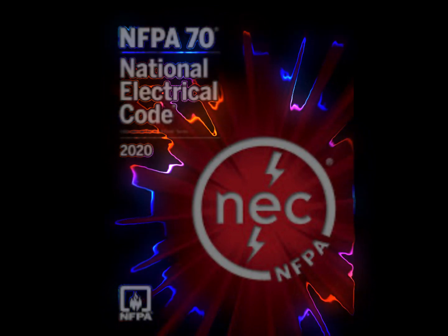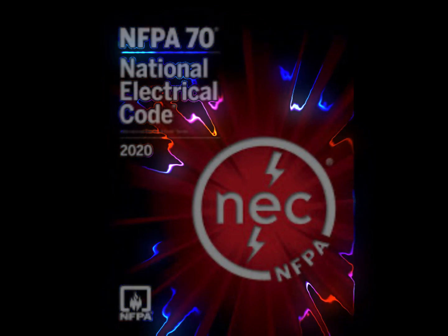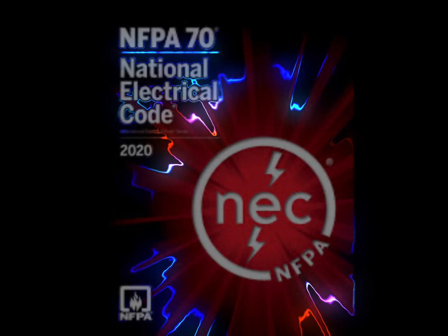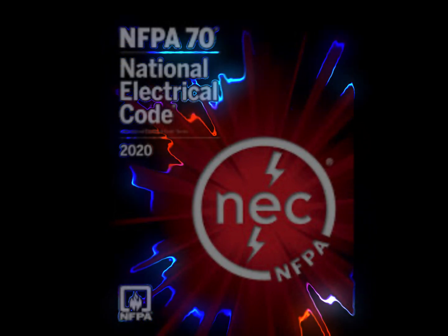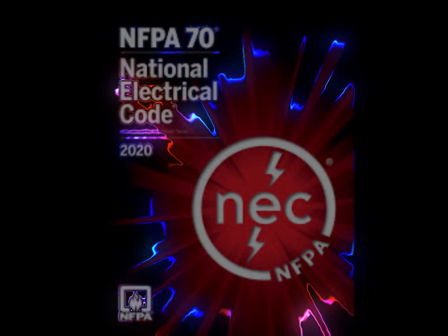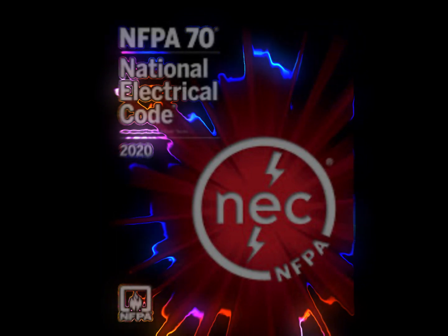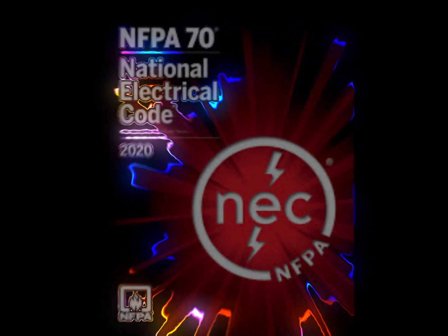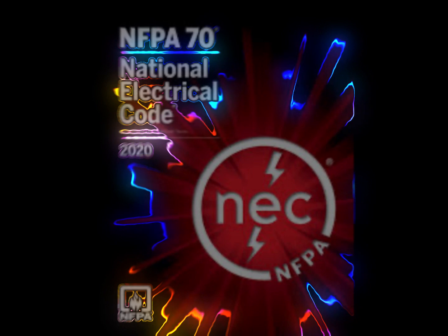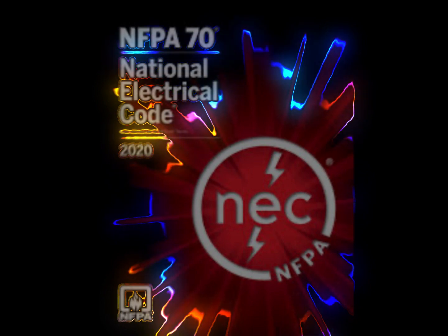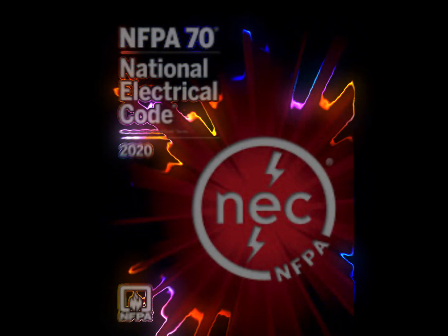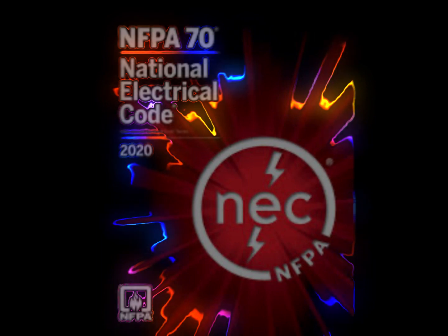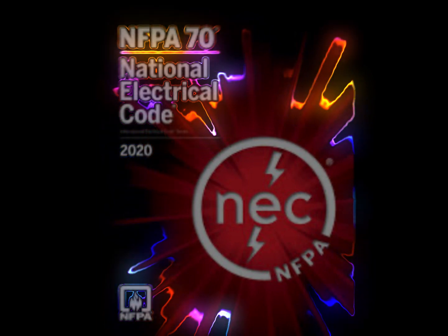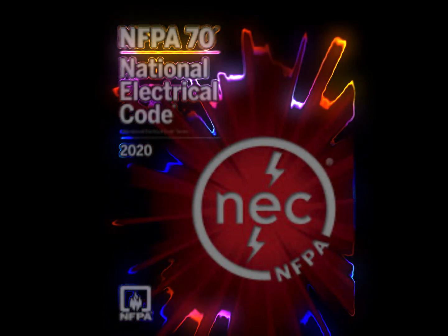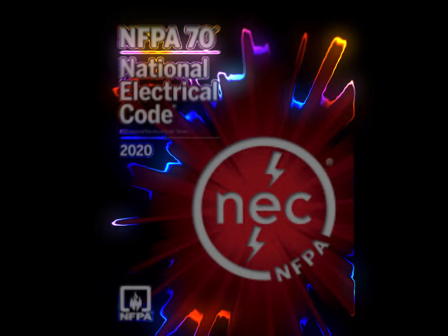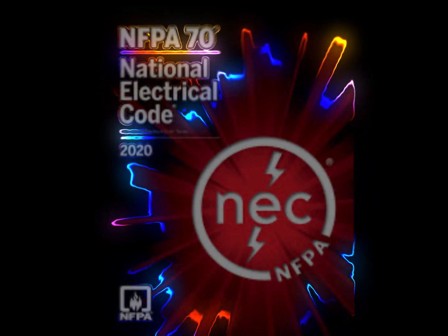It is to be noted that askarels of various compositional types are used. Under arcing conditions, the gases produced, while consisting predominantly of non-combustible hydrogen chloride, can include varying amounts of combustible gases, depending on the askarel type.